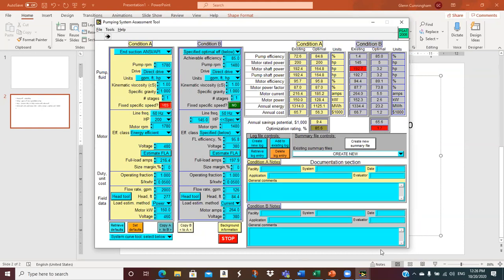192.63. Store that away. And then if I ratio those, it should give me roughly 72.6%, which is my pump efficiency. So recall 1 divided by recall 2, and 72.7. So there's a little bit of rounding digits. But basically, that's all this is doing for you, those simple calculations. But wow, put in the thing, bam, you got it. And you didn't have to look up a motor efficiency because it pulled one for you. Okay, so that's pretty nice.